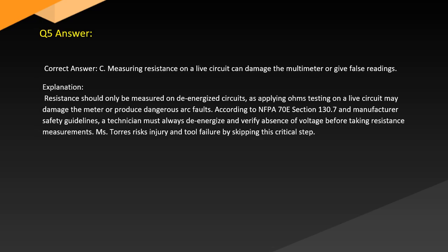Answer. Correct answer. C. Measuring resistance on a live circuit can damage the multimeter or give false readings. Explanation. Resistance should only be measured on de-energized circuits, as applying ohms testing on a live circuit may damage the meter or produce dangerous arc faults. According to NFPA 70E Section 130.7 and manufacturer safety guidelines, a technician must always de-energize and verify absence of voltage before taking resistance measurements. Ms. Torres risks injury and tool failure by skipping this critical step.